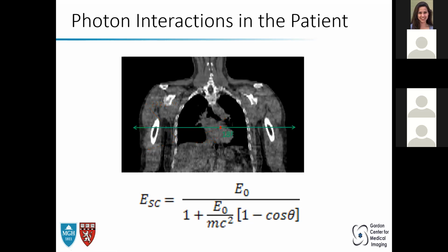Okay. Now, on the PET side, again, we've got F18, and instead of emitting one photon, we're emitting two at 180 degrees. Now, to detect the signal in PET, we need to simultaneously detect both of these. So the probability that we measure this signal is the probability that this photon does not get attenuated times the probability that this photon does not get attenuated. But this leads to a really nice feature that makes attenuation correction in PET somewhat simple.